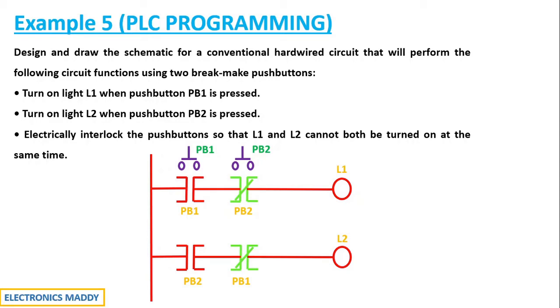Now one important thing to remember is the ones that are indicated in green that means the contact is actually energized because these are normally closed contacts. So they will be acting as short circuit before they are energized and once they are energized they will act as open circuit. So now initially they are not energized but these are acting as short circuits because these are normally closed contacts.